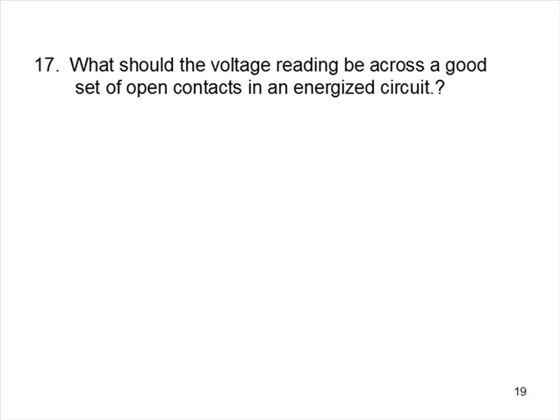What should the voltage reading be across a good set of open contacts in an energized circuit? Now the contacts are open, same circuit. Counter EMF, line voltage, the applied voltage, 0 volts. What should you read? The contacts are open. Applied voltage. You betcha, puppy. 18.